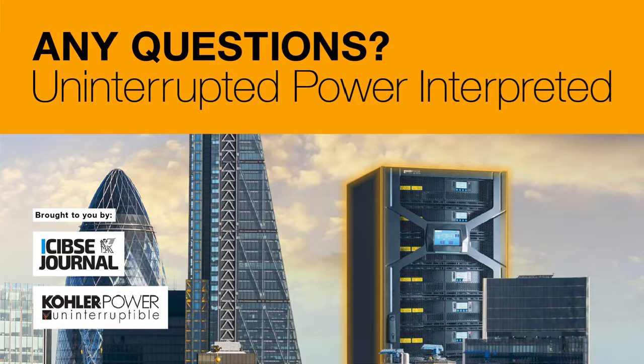Those state 20 degrees C as a target for battery location. Practically, how many people actually achieve that? Good question. We see a variety, to be honest. We always advise people to keep this at 20. A lot of the time we see around 20 to 22, but one of the big problems we see is people say it's 20 degrees in my comms room, but the temperatures in the actual room can vary. So it might be 20 degrees at the floor, but by the time it gets to the top of the battery, it's 25. So airflow around the battery is very important, because that 25 degrees is taking years off your battery.